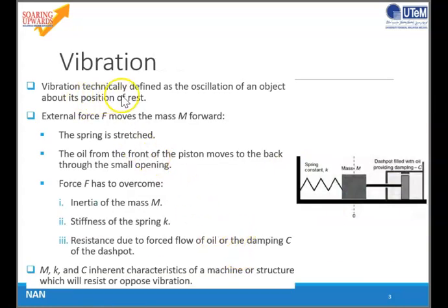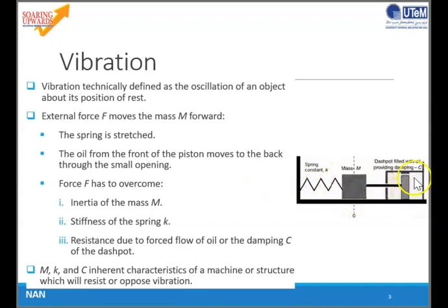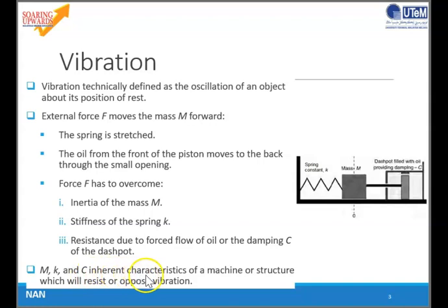Vibration is technically defined as the oscillation of an object about its position at rest. As you can see from this diagram, the external force F moves the mass forward, and the spring is stretched, so the oil from the front of the piston will move to the back through the small opening. The force F has to overcome the inertia of the mass M, the stiffness of the spring K, and resistance due to oil flow, or the damping C of the dashpot. M, K, and C are inherent characteristics of a machine or structure which will resist or oppose vibration.